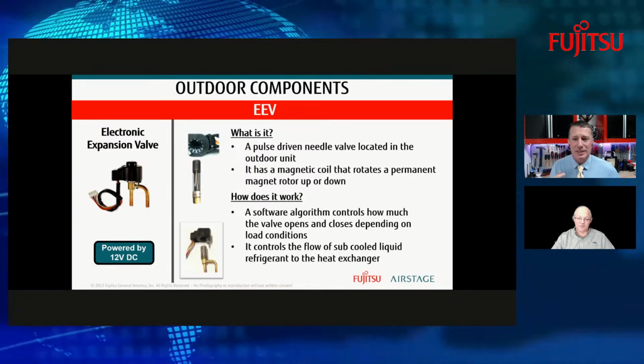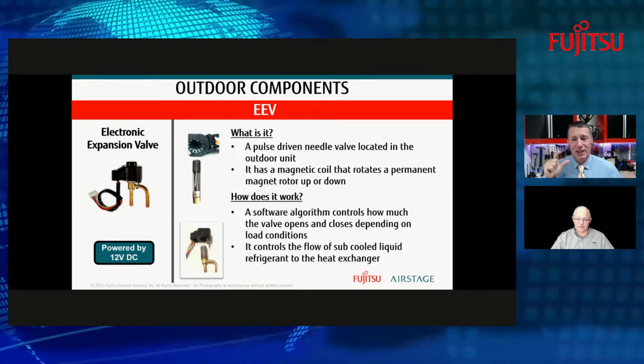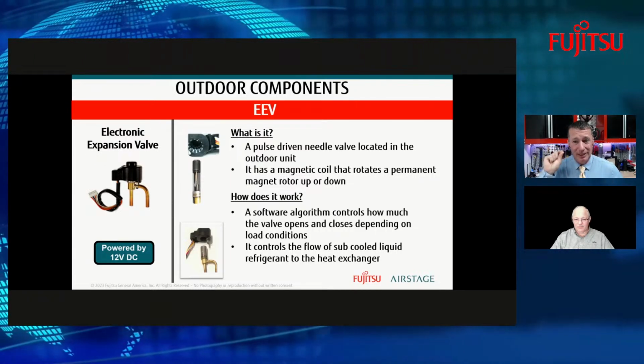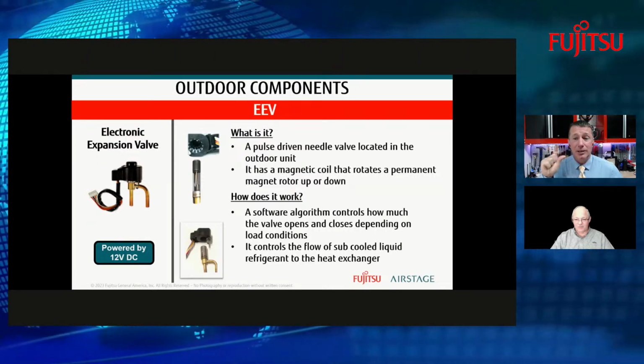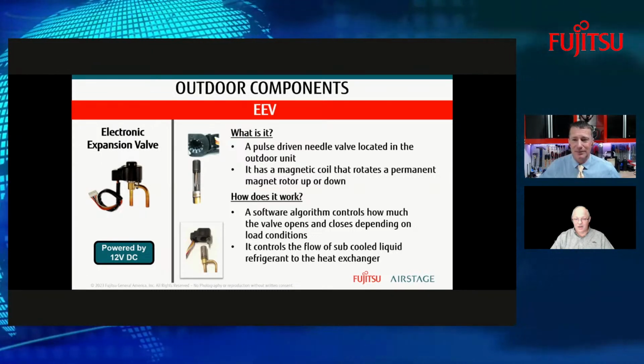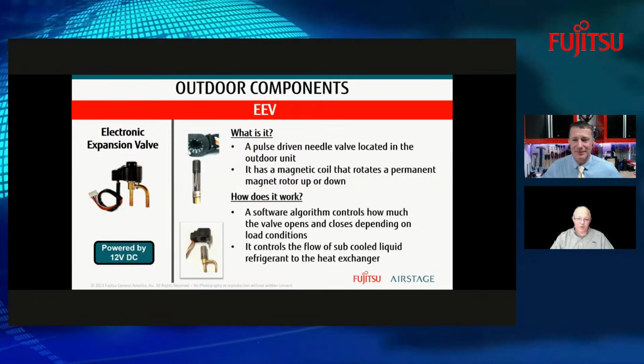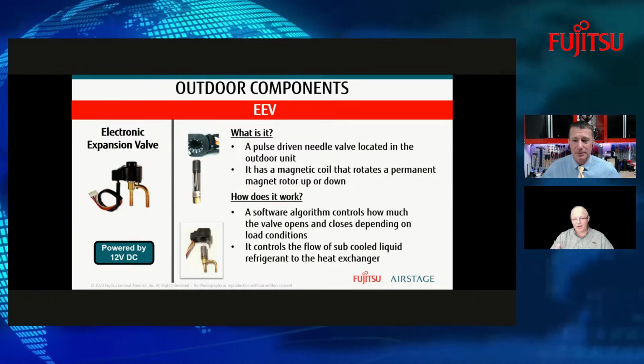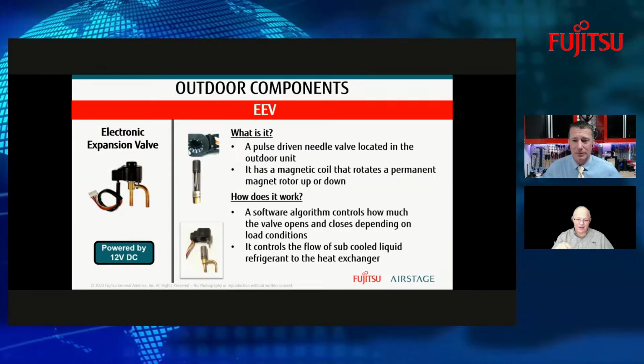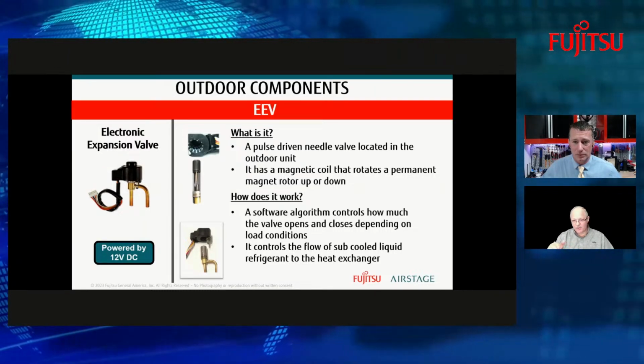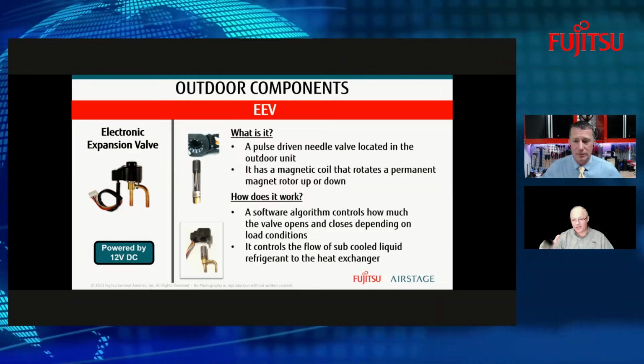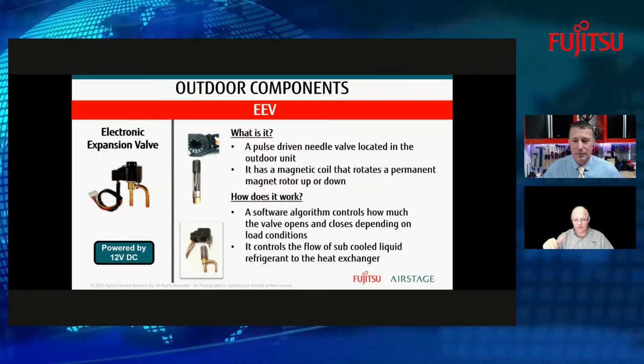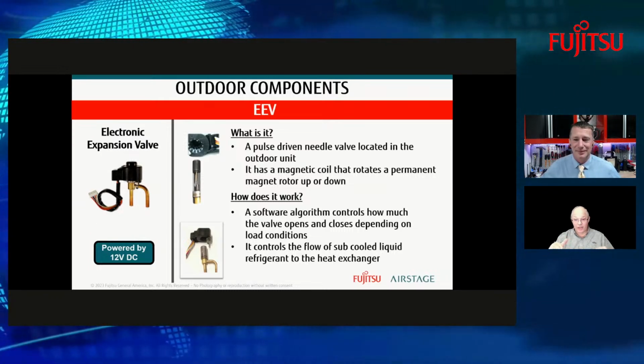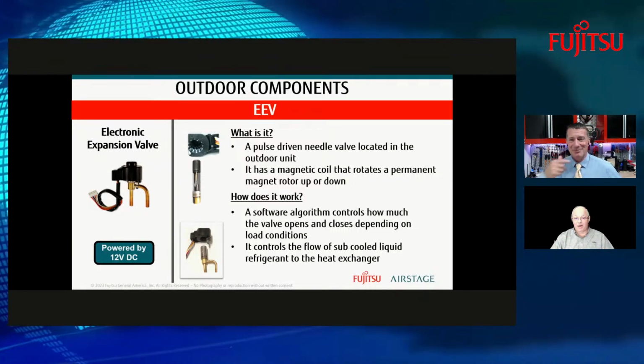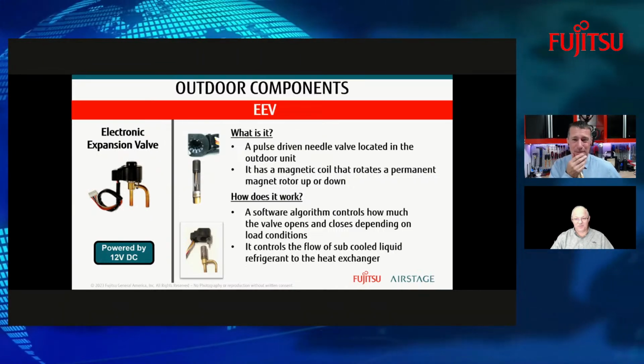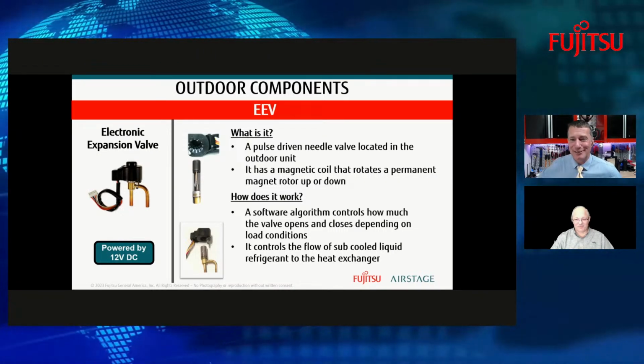Now, one question I've always had, and I've never had the opportunity to ask a manufacturer: are we able to go from 0 all the way through 100? Can we be completely closed and 100% open on our EEV flow valve? It's doubtful that you would be fully open to the full steps that are there. From what I've seen in our literature, different models will open to a certain number. Maybe it's 420, maybe it's 460. It'll never hit the 500. It's designed to open to whatever the engineers have decided. Okay, that makes more sense now, because I kept seeing different stepping, and I thought, surely there's not that many different valves out there.